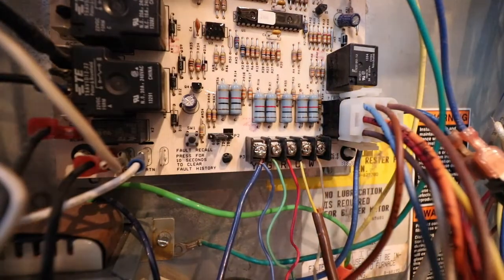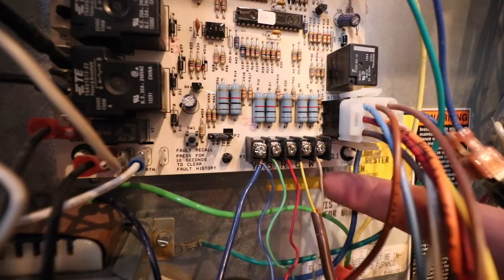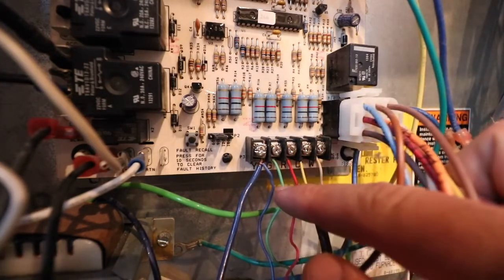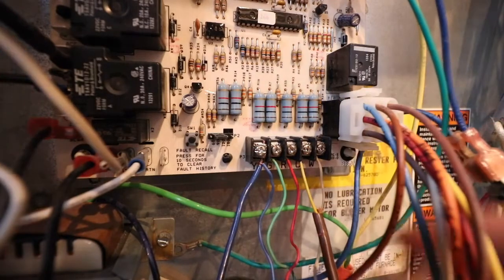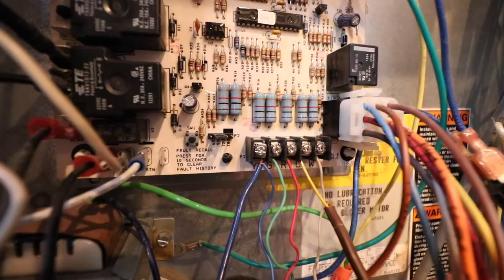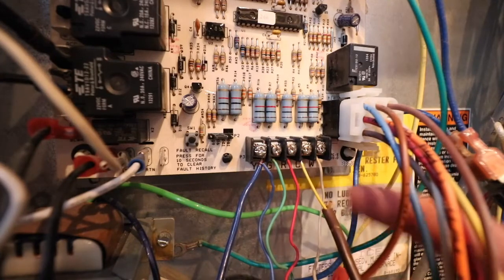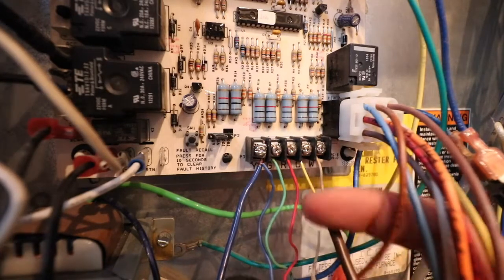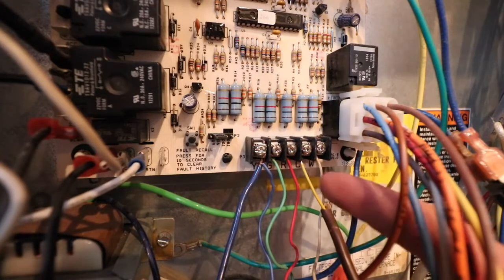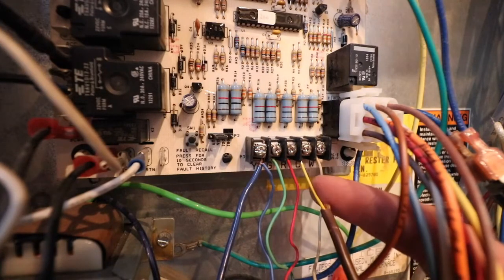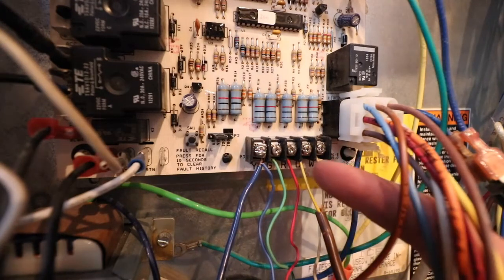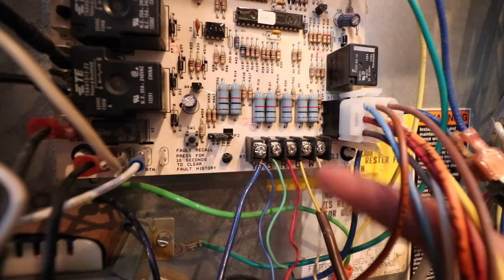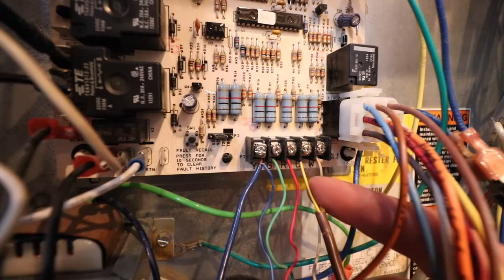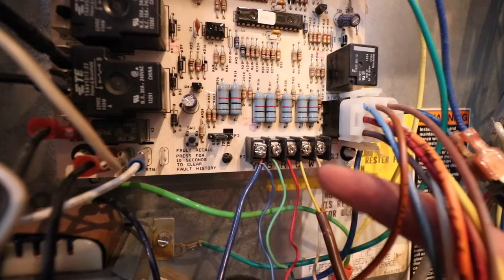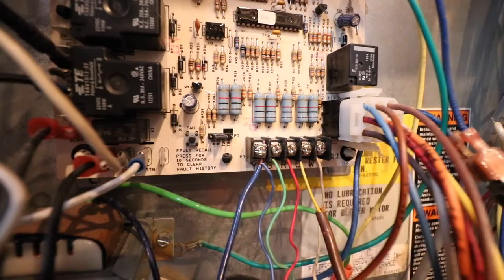Now, we've got the same 4 wires here. We have this white one, this red one, the green one, and blue one that were all up at the thermostat. But now there's a little bit of a difference because there are 2 wires here. We have this extra yellow wire here and this extra blue wire here. Well, that's because these 2 wires are used to send the signal to the air conditioner compressor at the control board. So we've got these connected from the control board up to our air conditioner compressor that is outside on top of the house or behind the house. So that's what these extra 2 wires are for typically.